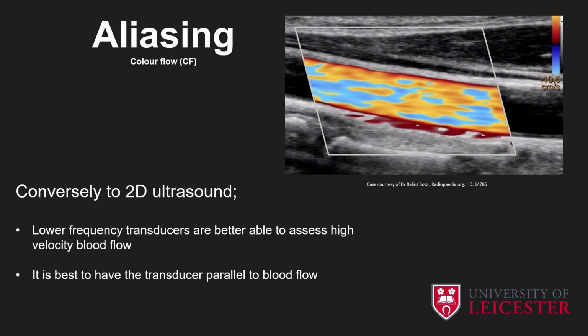I also just wanted to mention aliasing, which is an artifact that is particular to Doppler. It happens when a maximum velocity is exceeded, and factors that cause it are a high frequency transducer, inappropriate angle of the transducer or the beam, and a large sampling volume. You just see that the colour flow is mixed between red and blue.